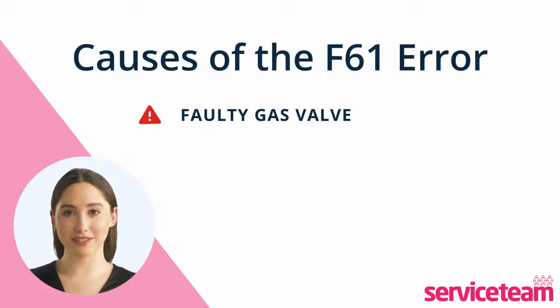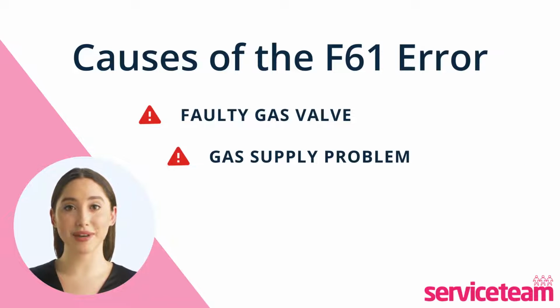Another potential reason for the F61 fault code is a gas supply problem. This can mess up your boiler's operation. If there's not enough gas pressure or something's blocking the gas line, the gas valve won't get the fuel it needs to fire up the boiler.